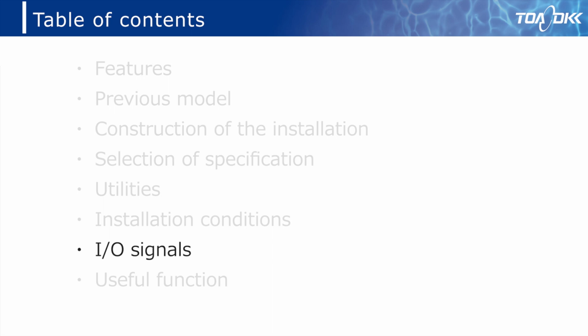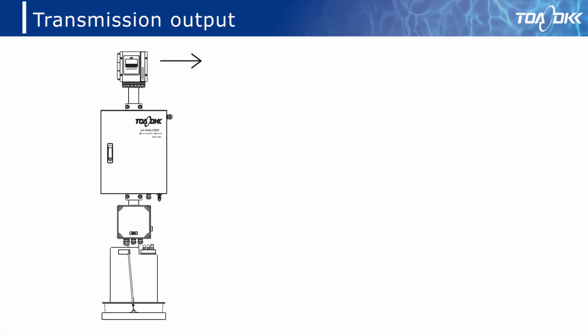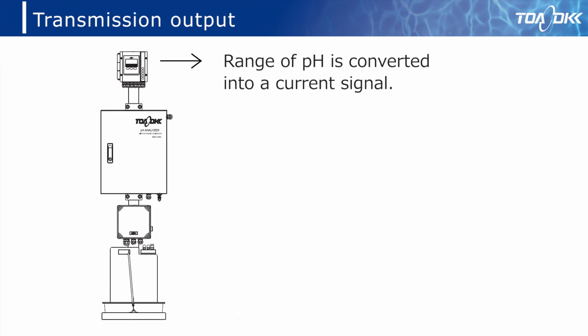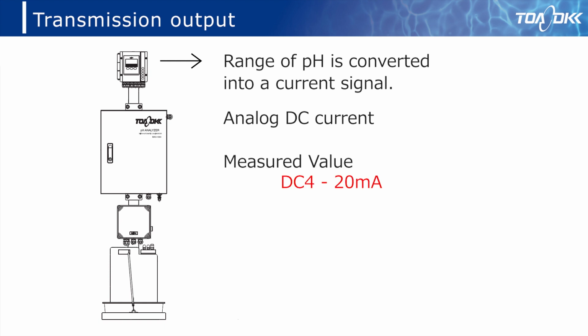This section explains the input and output signals. First, the transmission output is explained. The transmission output converts the range of pH into a current signal. The signal is then output. The default is pH 0 to 14 for DC 4 to 20 mA.